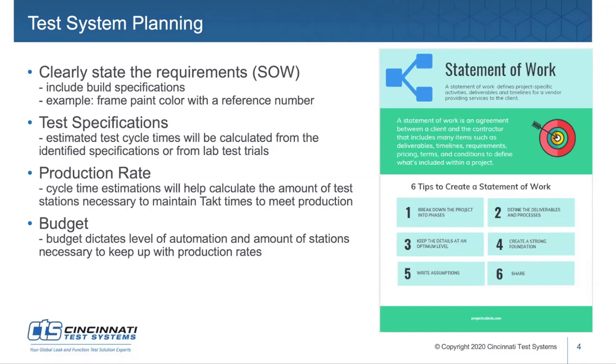So what's next? Oh yeah, so then you take leak rate and you understand what a production rate is, understand the customer's takt times and production rates, and then calculate estimated test cycle time, and then put that back into that calculation and say, okay, will we get throughput for this program with one station, or does it take 2 or 3 stations? And then, budget allowing, does it require automation, or is it a manually loaded, unloaded operation? So budget's always necessary to understand as you dive into a project and what the throughput requirements will be.